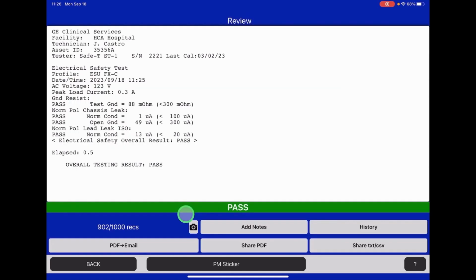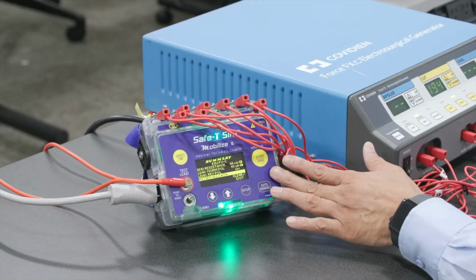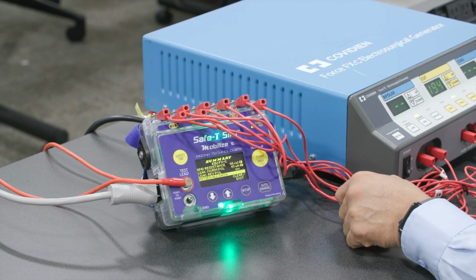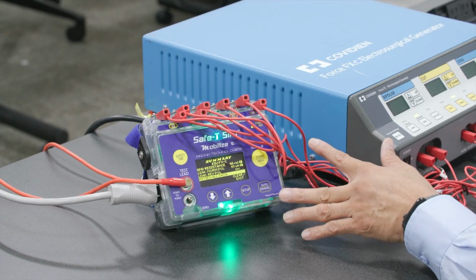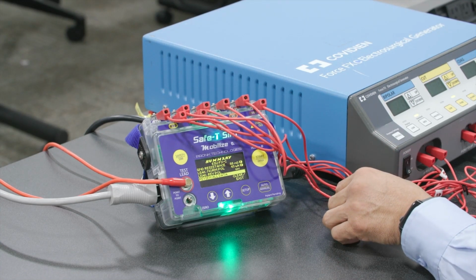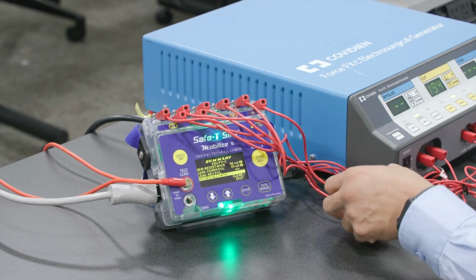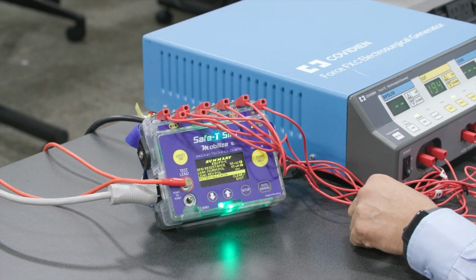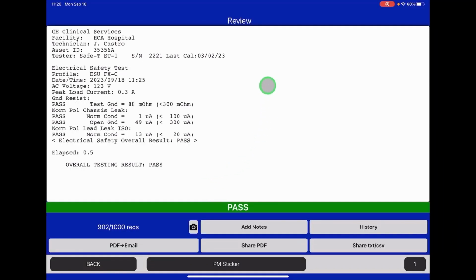And once it's done, you'll see on the app itself and on the safety analyzer itself as well, a green indicator letting you know all of the tests have passed. If any test has failed, you'll see that indication on the analyzer and on the app that a test has failed, that you'll need to diagnose and troubleshoot as to what could have failed on the unit. Then of course on the app you have a complete report of everything that was tested on this Force FXC, including the serial number of the equipment you used, the date that it was calibrated, and then below that are all of the tests that were required per the manufacturer's procedures, with your measured values here in the center versus the limits here on the far right. So we've completed the electrical safety test on this Force FXC.